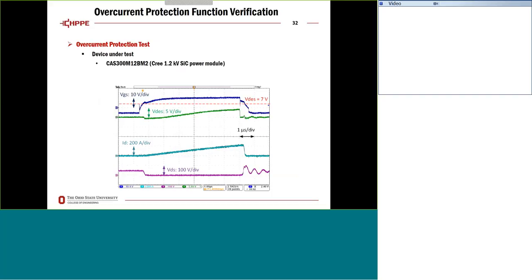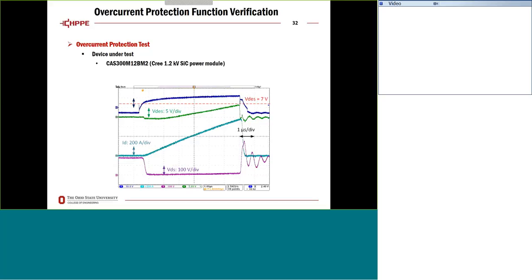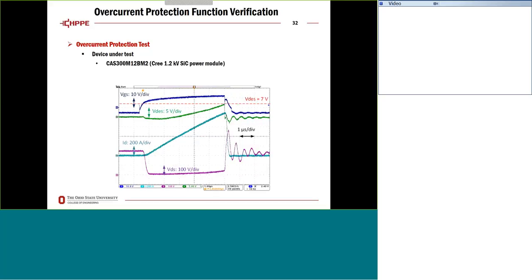This is the test of the gate drive board with a low voltage device, since we only have 2 samples of the 4.5 kV module at the same time. I didn't want to run the short circuit test with a limited number of modules first, so we used a 1.2 kV silicon carbide MOSFET device to verify the short circuit function. You can see that as the current, the green curve, goes up, it's eventually protected. This time we didn't implement soft shutdown, so at the protection point we still have a hard shutdown.